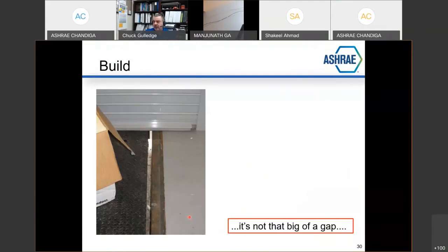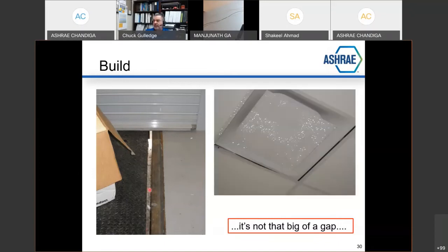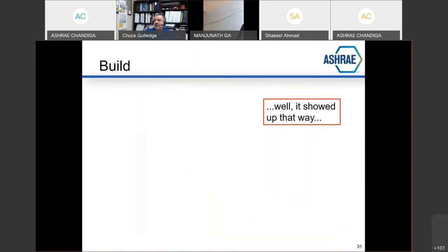It's not that big of a gap. Okay, that's a debatable point, but this happens to be in a hot, humid climate, and that is the great outdoors. And inside where I am, it's a comfy little space where they're trying to maintain building dew point and temperature control. And look what happens when you have that opening and the differential vapor pressure of the outdoor environment to the indoor environment. The ceiling diffusers were raining, all because the moisture level was so high in this space and the surface temperature of this was below the dew point. And you know what happens when that occurs? It rains. Okay, great construction. Well, it showed up that way.